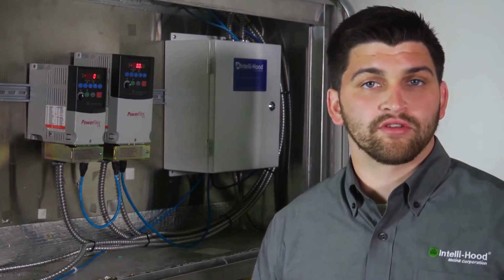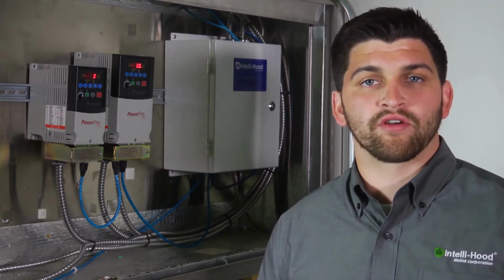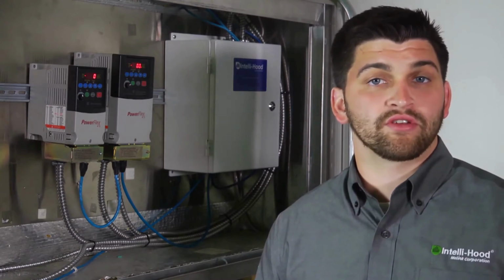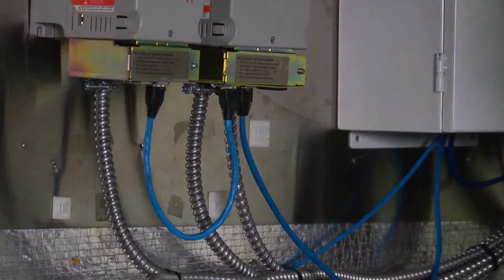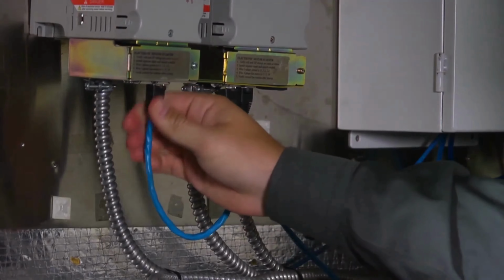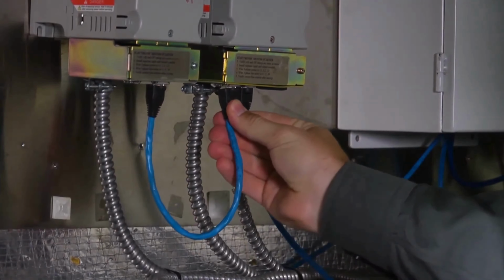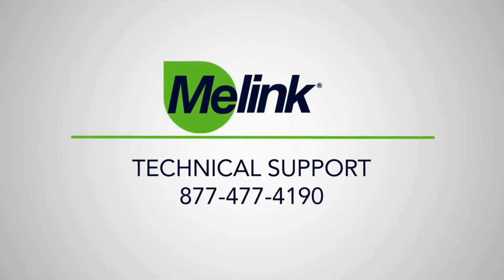If your Intelli-Hood touchpad is displaying VFD lost comms, it usually means the drive has lost power or the connection has been broken either physically or by some programming change. Verify the Cat5 cable is securely connected at the drive and the system controller, and if further investigation is needed, contact our technical support for assistance.